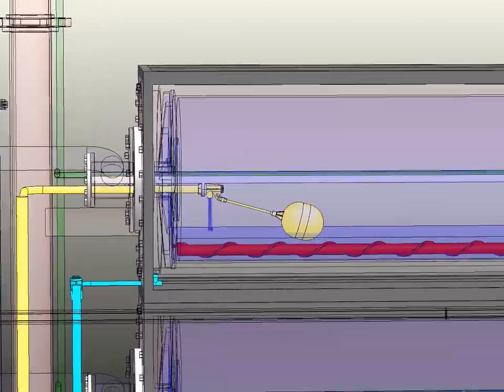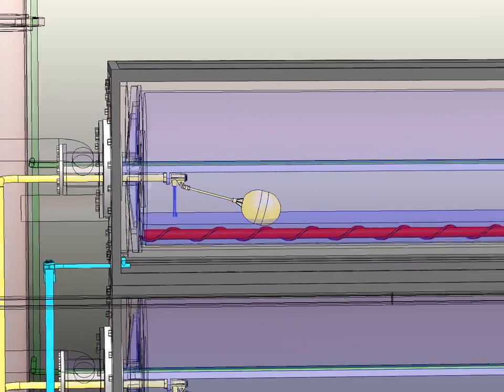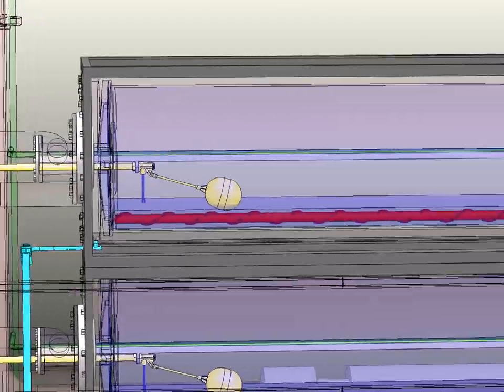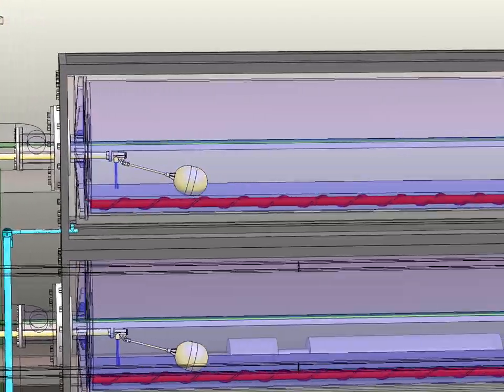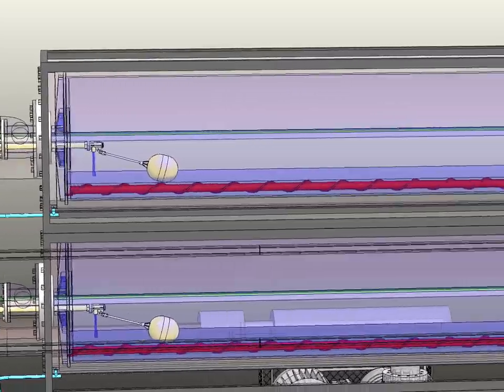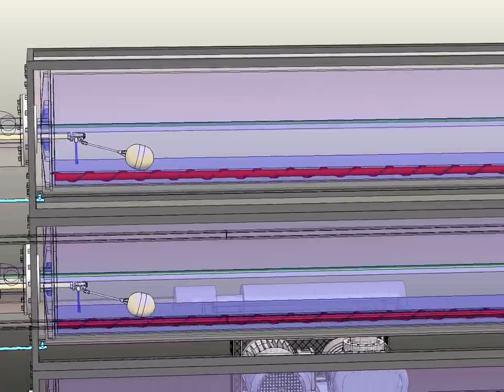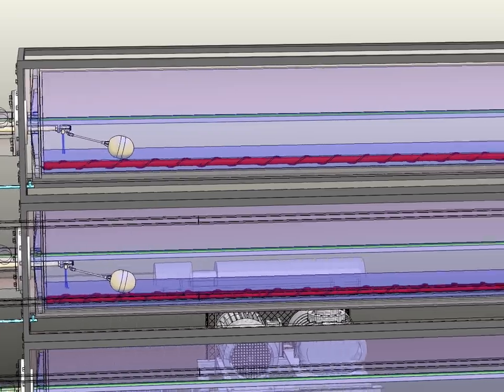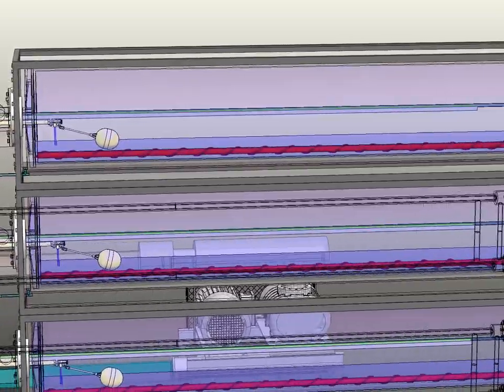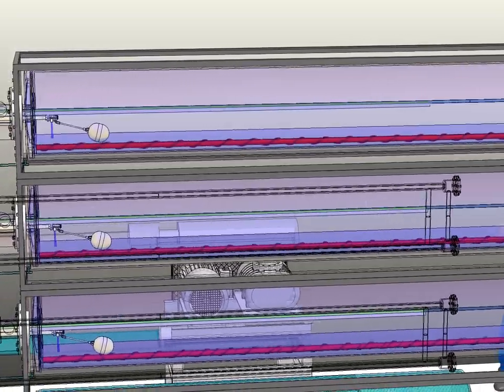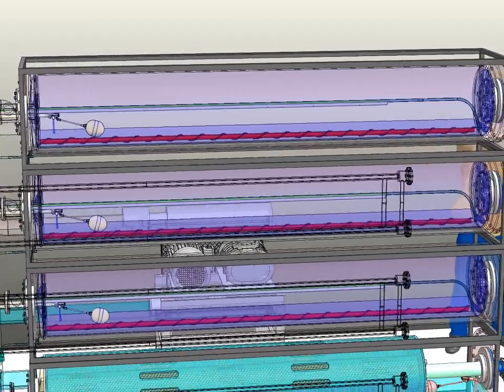with a spiral winding. If it is impossible to move this rod in the axial direction, the spiral winding works like an auger, which not only cleans the resulting sediment particles, but also transports them to the concentrate discharge point. This prevents particles from accumulating in the concentrated solution and makes the evaporator resistant to scale formation.